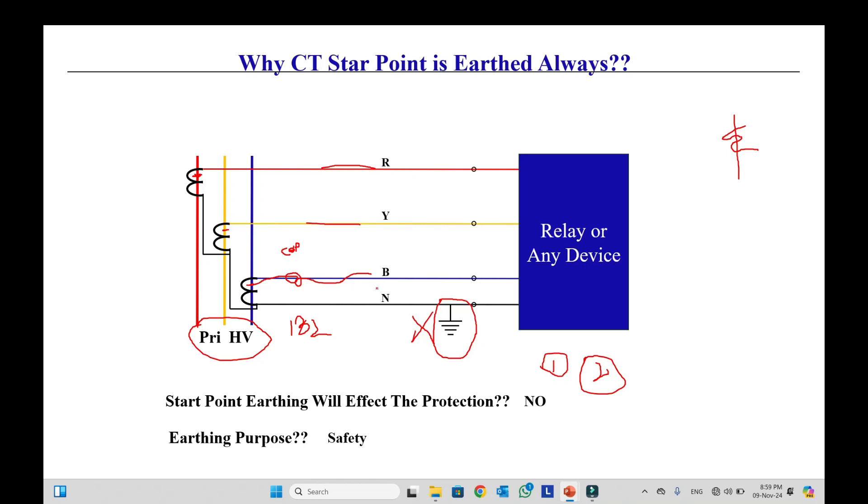And this voltage, if we do not earth it, it will remain in the circuit. And it's also not the intended purpose that CT secondary should have voltage. And it's also dangerous for the relay and also not good for protection or any device connected to the CT. So with the earthing, this voltage will drain out, and there will be no voltage in the CT secondary side.